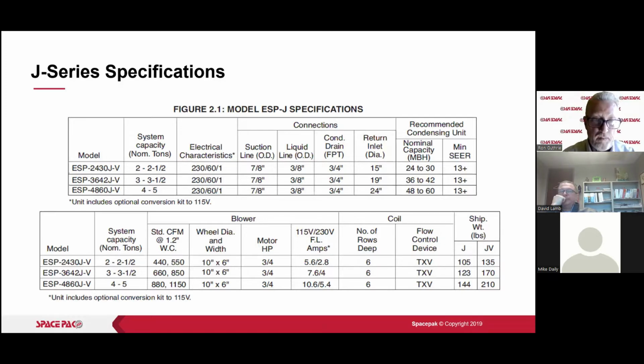And if you look in the bottom chart there, again, they're using 220 CFM per ton as the nominal tonnage or nominal CFM. I would stick with 250 CFM per ton. You want to be higher than 220 because we never get the complaint that we have too many CFM on the system. So we want to try our best to shoot for that 250. There's that wheel diameter 10x6 with its backwards inclined, and it's the same blower on every one of those units. So what we've got is a greater speed and more cabinet to move the air through as well, so we can get more CFM through at those same pressure drops. 6-row coil, we'll talk about that a little bit more in the TXV as well.